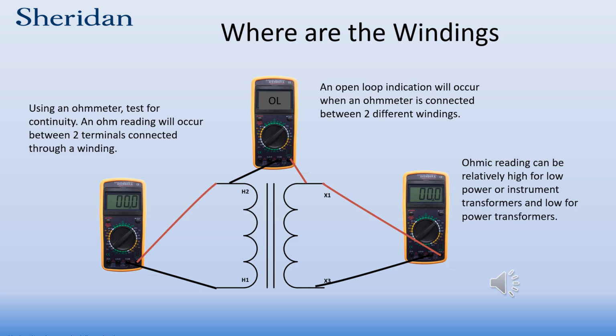One way of determining which is the high voltage side is that the high voltage side will have a greater resistance than the low voltage side, usually because of the many turns of very light wire, whereas the low voltage side will be expecting more current than the high voltage side and will have a lower voltage, and its resistance will be lower.